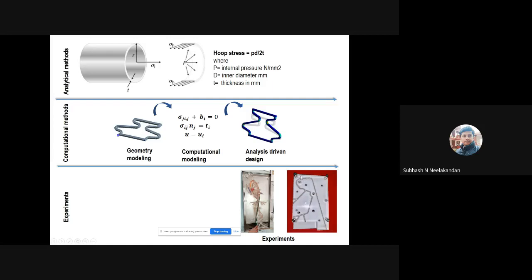Number one, we can make engineering test systems, which will be similar to the biological environment where the device is intended to work. For example, this picture on the right hand bottom side shows a pathway created by the engineering team, and this pathway mimics the path through which the device will be inserted inside the blood vessel. This is basically a blood vessel and will capture the tortuosity, the twists and turns of the anatomy. So either this can be done, or number two is a simulated system.